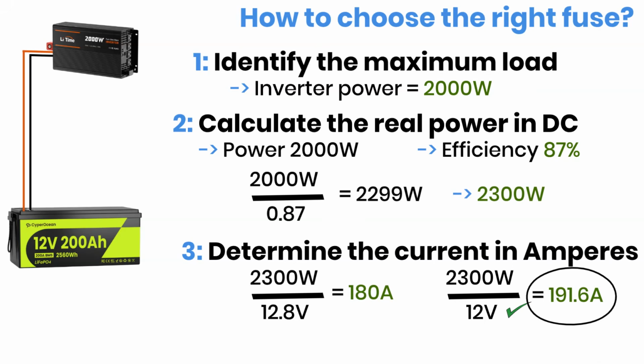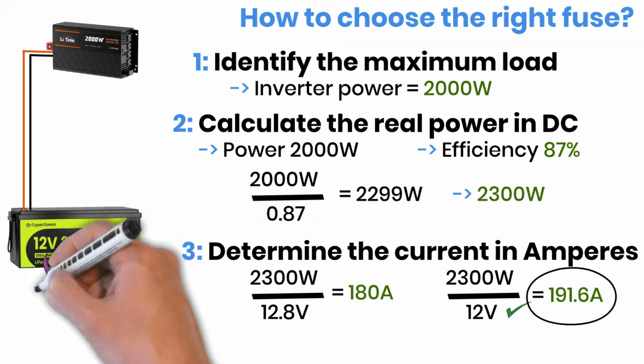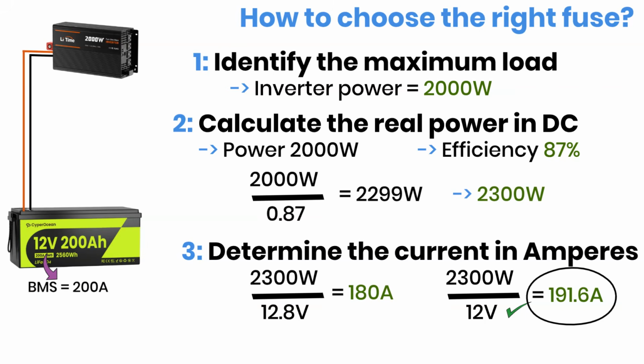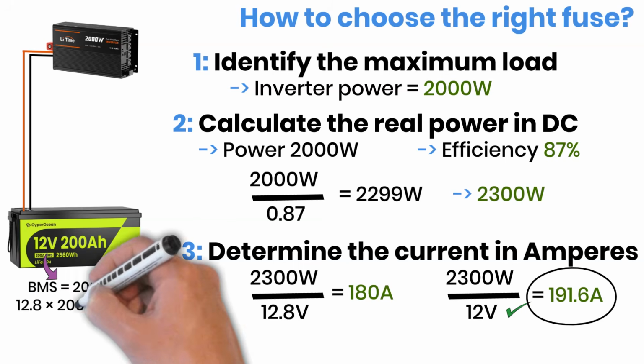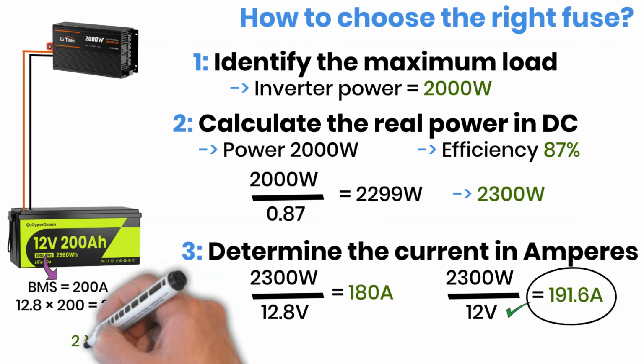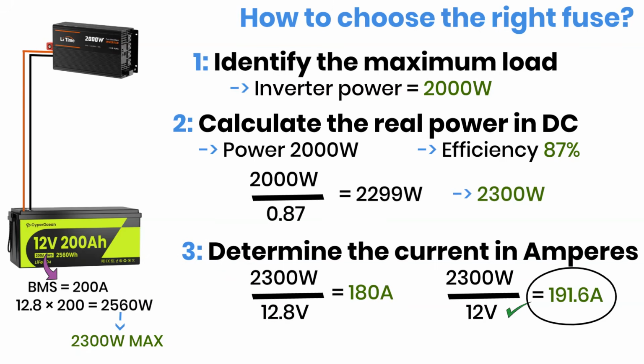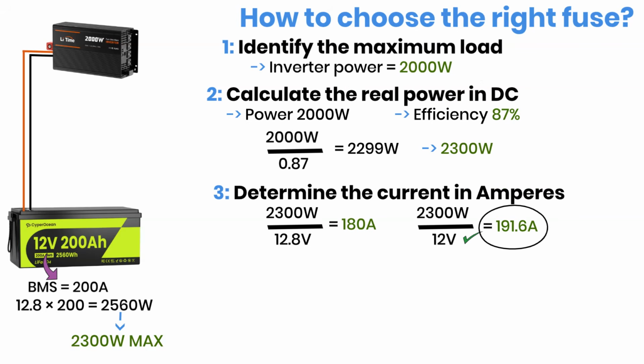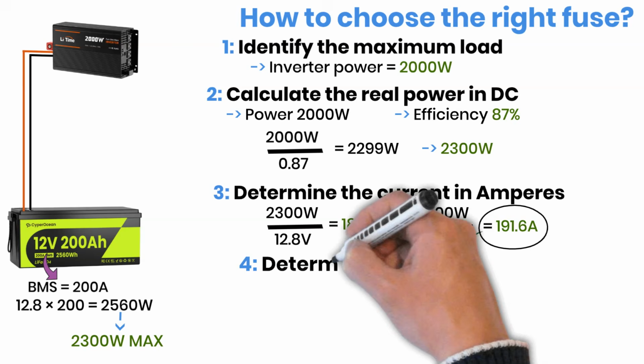Before moving forward, we should check if the battery can handle this. Let's say the battery management system is rated at 200 amps. That means we are getting close to the limit, but still within range. There's only a small margin left, so this setup is okay, but not something you want to push beyond full load for long periods. Now comes the fuse sizing.